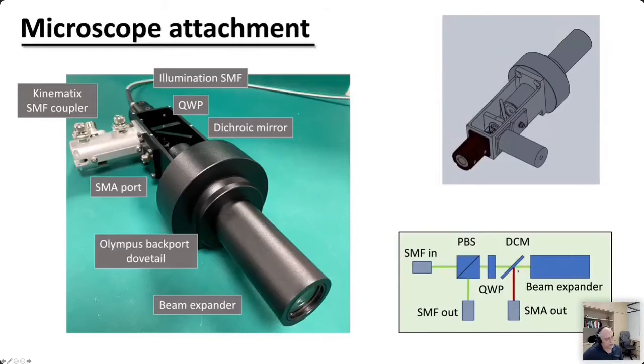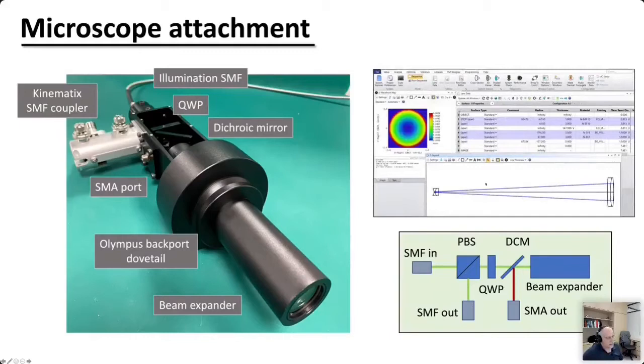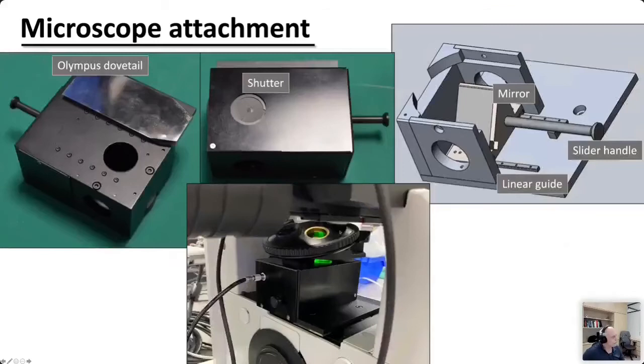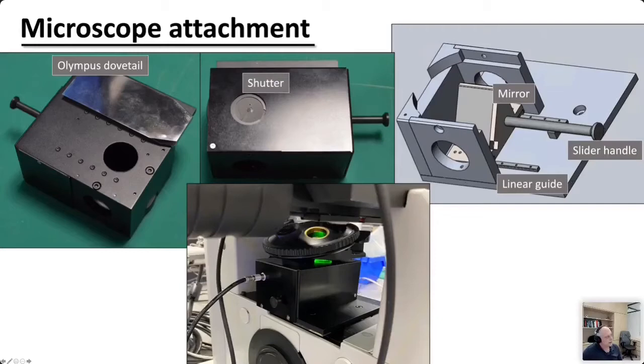This is basically the design: we have the single mode fiber coming into the system, a polarizing beam splitter, a quarter wave plate, a dichroic mirror, and that goes into a beam expander. When the light comes back from the microscope, we have an SMA output for a fiber — that would be the output for the Raman spectrometer — and the light runs back and couples into the single mode fiber. This is the manufactured version, and it slides into the Olympus microscope. It allows us to slide in and out a mirror to couple light into the microscope, and has an electric shutter.